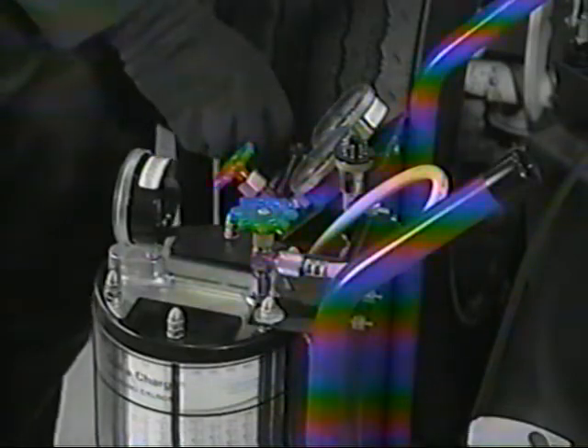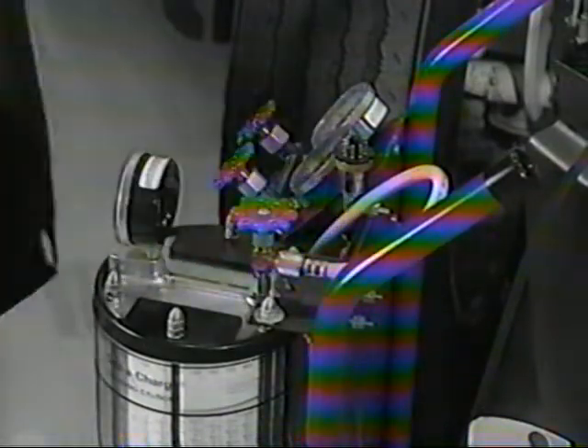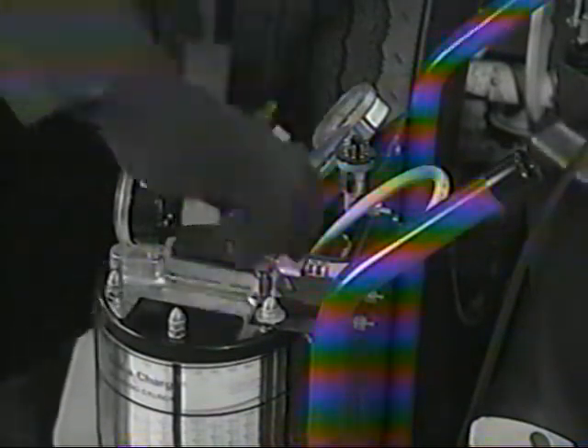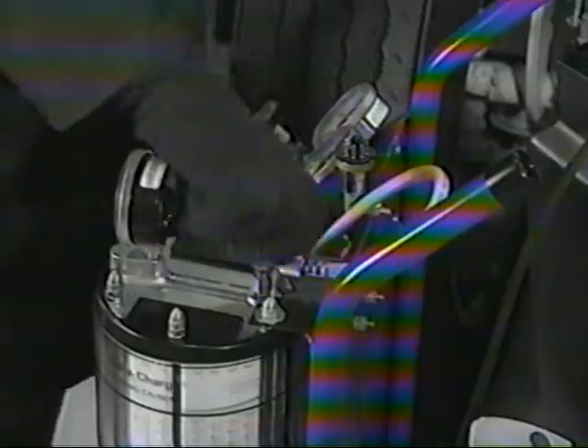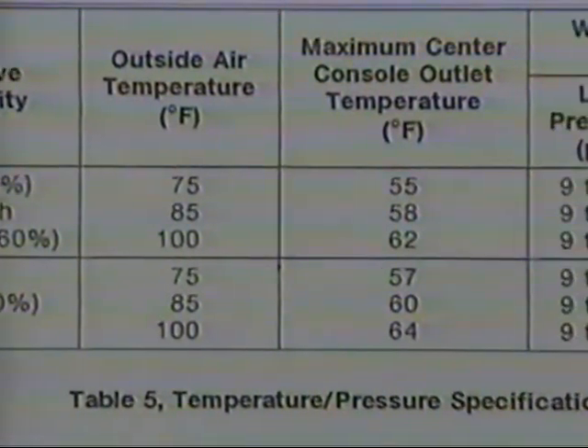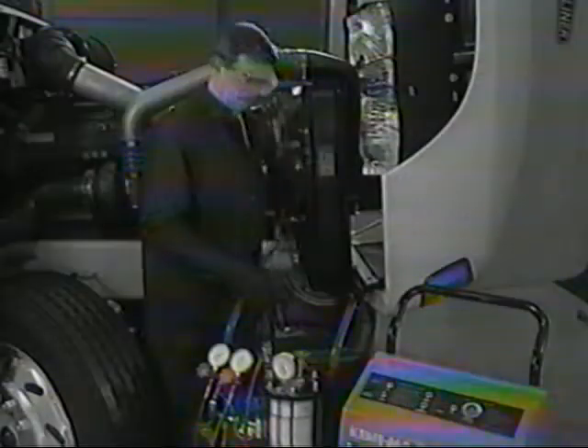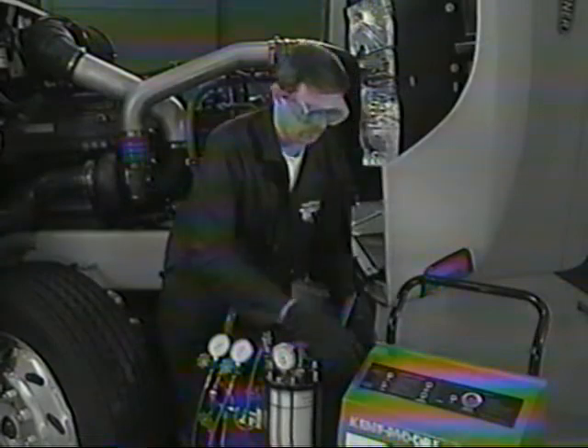If vapor charging, open the manifold low side hand valve to allow R12 vapor to be drawn into the system while the compressor is running, with the engine running at 1500 RPMs. When the system is fully charged, close the manifold low side hand valve and turn off the refrigerant supply to the manifold set. Run the air conditioner at maximum to check the gauge reading and outlet air temperature. Refer to the specification tables in the service manual for the temperature-pressure specifications. Disconnect the manifold set. Finally, recover the refrigerant from the charging station line. This completes our look at the Freightliner pre-service checks and service procedures for the R12 air conditioning system.